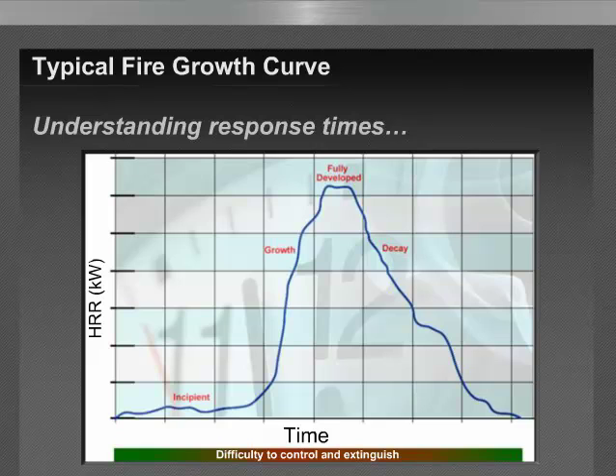The smoke development in this stage is generally not visible to the human eye, has considerably low heat release rates, being extremely buoyant, with migration easily influenced by air currents. If we follow the incipient stage, we get to the growth stage, which could be expected to increase quite rapidly, leading to the fully developed stage, which is generally the case. As fires grow in size, the energy release rate increases to peak value, and once fully developed, fighting fires becomes significantly more difficult, and of course the consequences potentially much more severe. Smoke detection categories will be related to how far an event develops before it is detected.